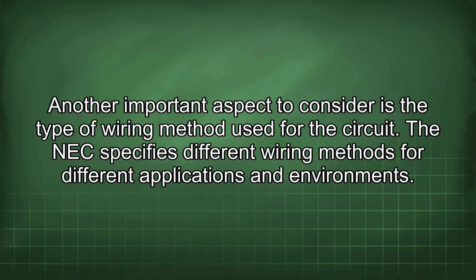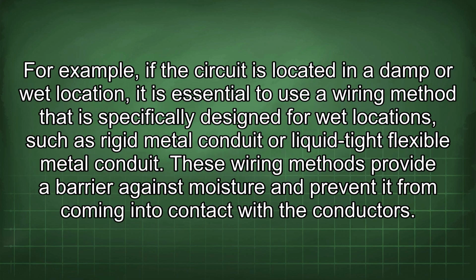Another important aspect to consider is the type of wiring method used for the circuit. The NEC specifies different wiring methods for different applications and environments. For example, if the circuit is located in a damp or wet location, it is essential to use a wiring method that is specifically designed for wet locations, such as rigid metal conduit or liquid-tight flexible metal conduit. These wiring methods provide a barrier against moisture and prevent it from coming into contact with the conductors.